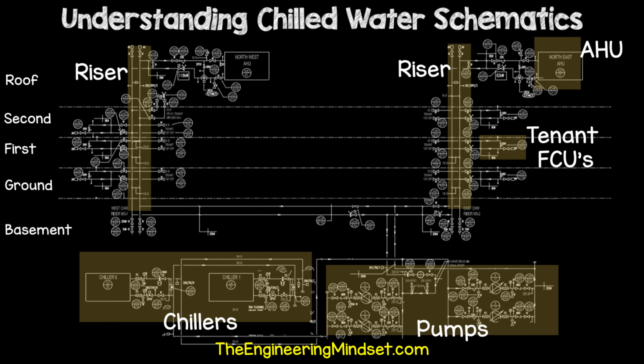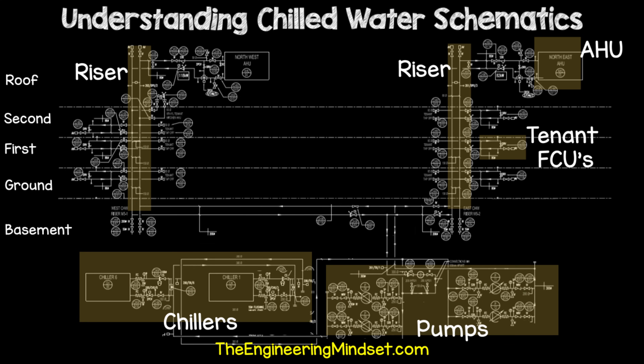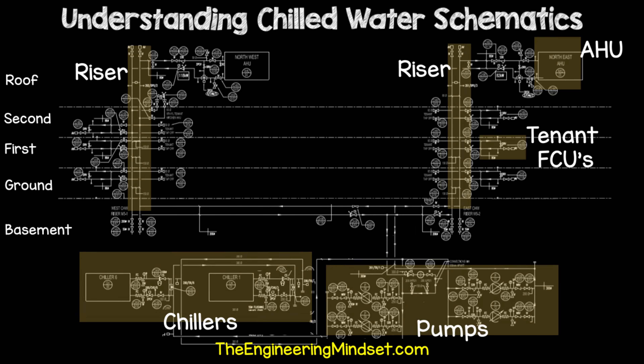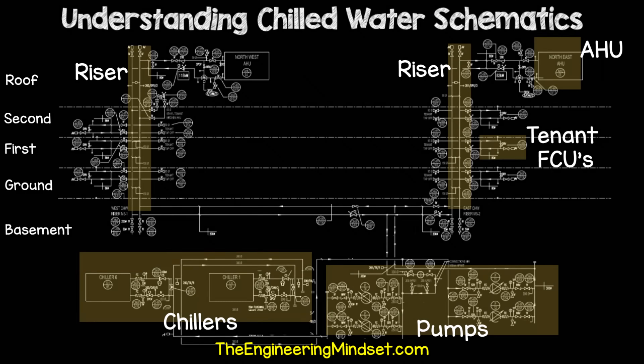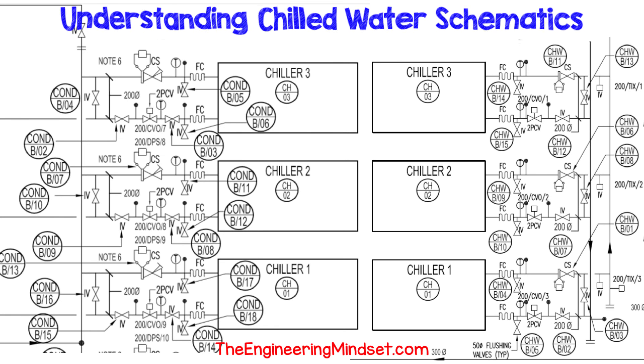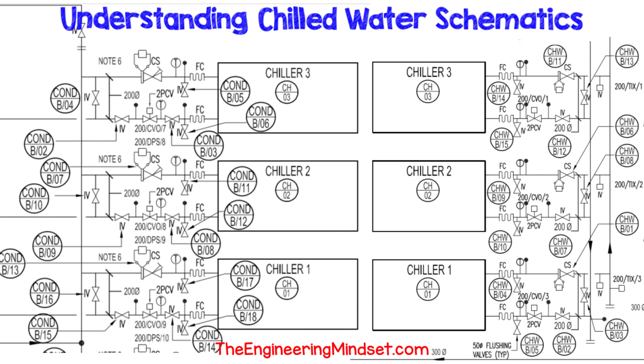Whenever I'm reading a schematic, I always start by locating the chillers, the pumps, the risers, the AHUs, and the cooling towers. This shows you how the system works, how it's all connected, what type of system it is, and where each part is located. The schematics can be quite cramped, and you'll sometimes need to see through this information to be able to follow the system.